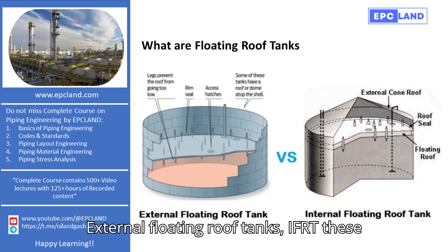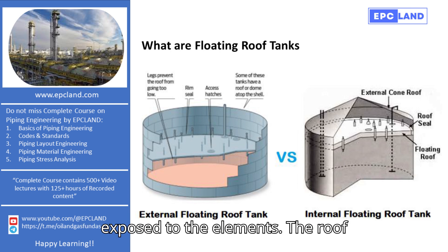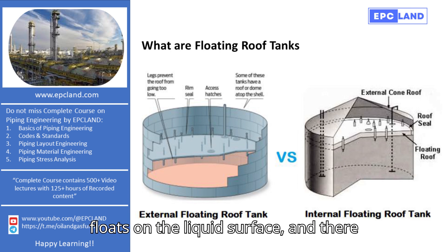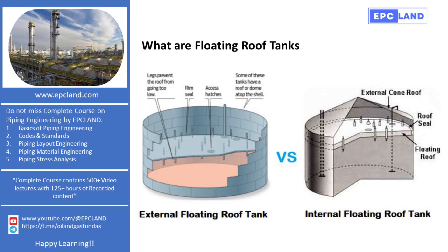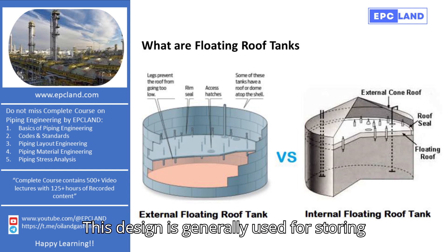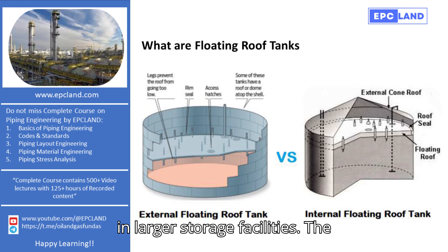External floating roof tanks, or EFRT: these tanks are designed with the floating roof exposed to the elements. The roof floats on the liquid surface, and there is no additional fixed roof above it. This design is generally used for storing less volatile liquids and is often seen in larger storage facilities.